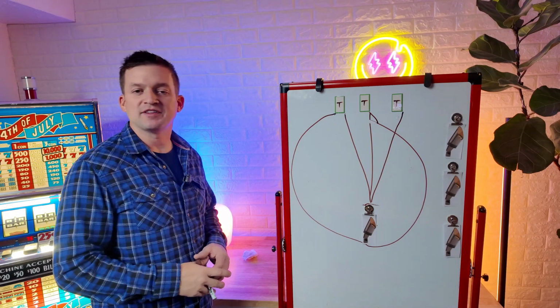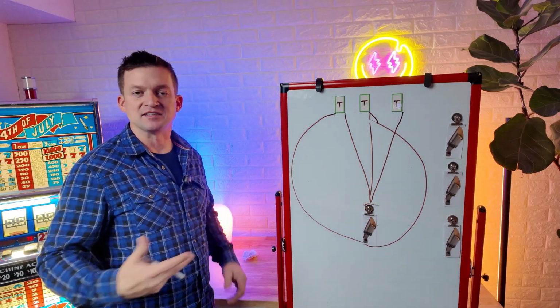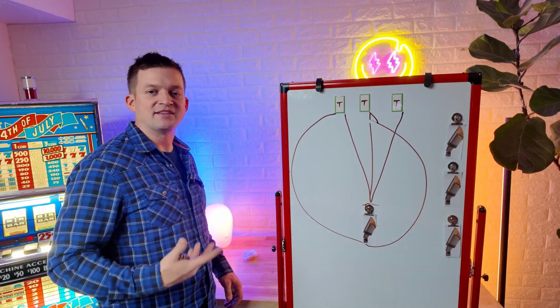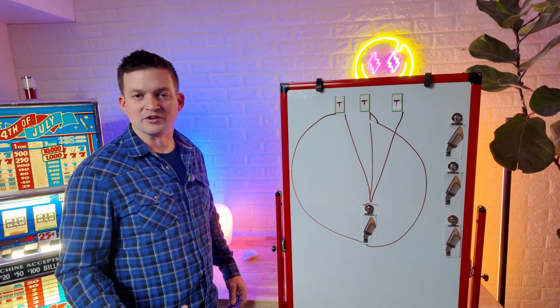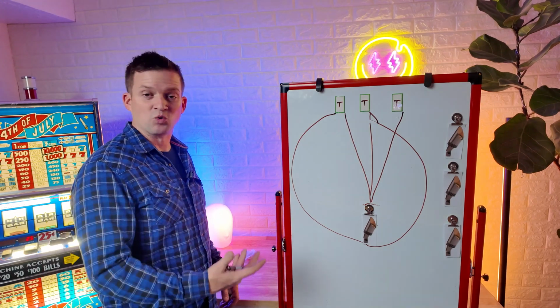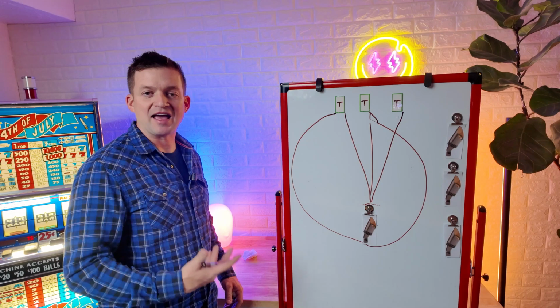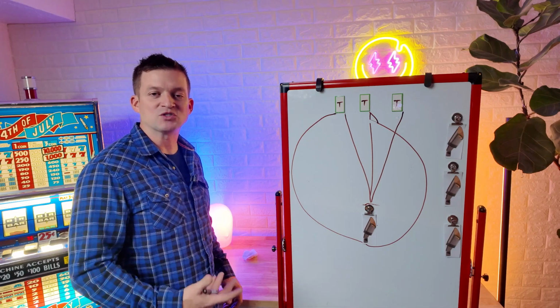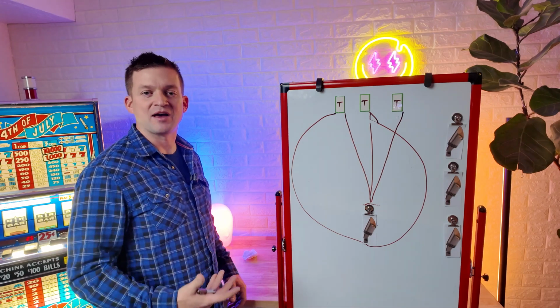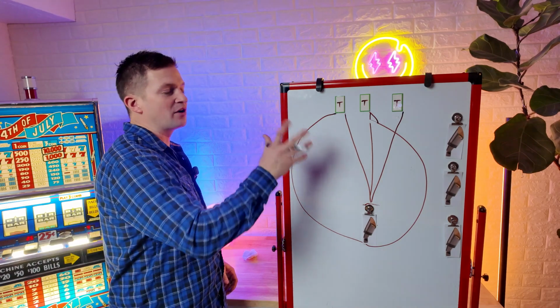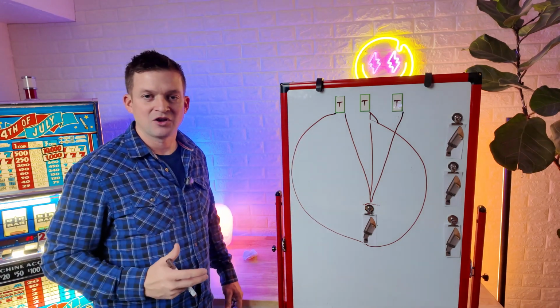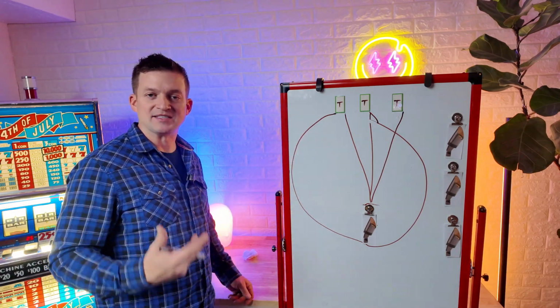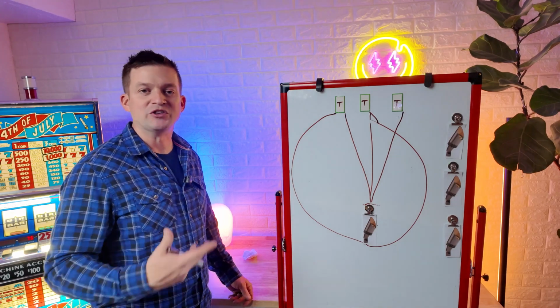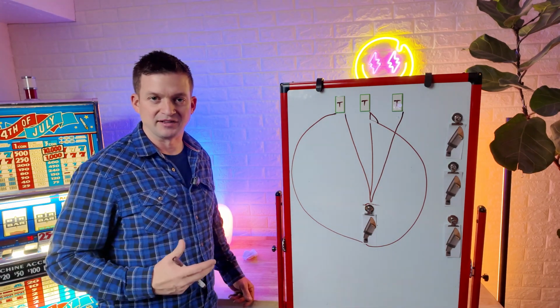Because our scope of work did not allow for making repairs to the existing system, we decided to identify an alternative fixture that we were able to test the wiring and make sure that we could accurately determine how many watts were in fact on that wire, and to make sure that that wire was not commingling with other transformers in the same space. Once we identified a wire that we could safely add the needed wattage to, we utilized that wire to power our string lighting system.